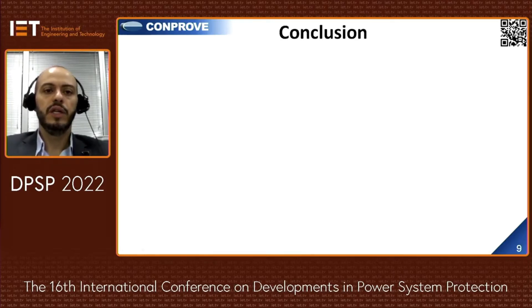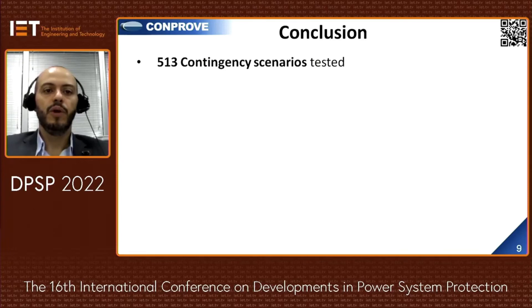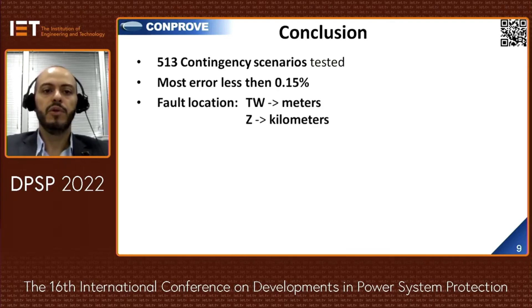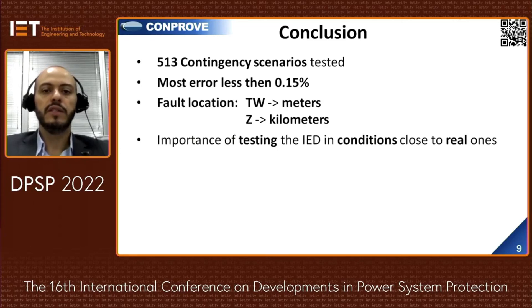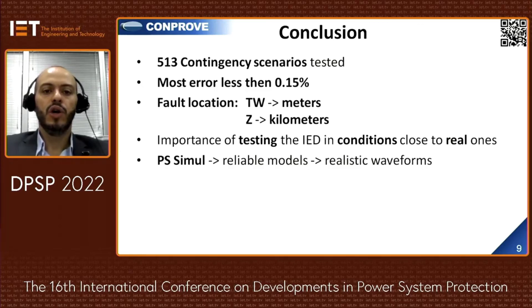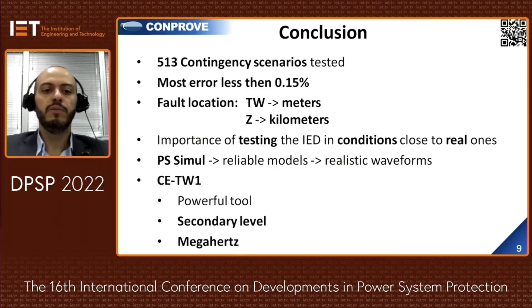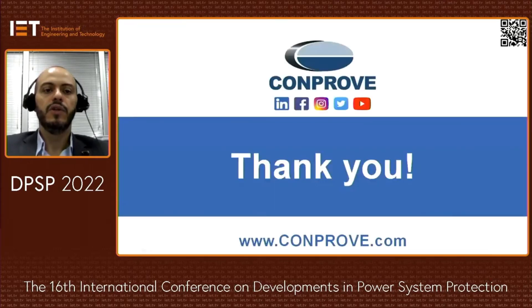Conclusions: 513 test injections were performed. Most location errors in meters were less than 0.15%. TW location errors are on the order of meters, while impedance methods reached the order of kilometers. It is very important to test the IED under real conditions. The power system simulator, with reliable models of electrical system components, results in realistic waveforms. The CETW1 proved to be a very powerful tool due to its ability to generate voltage and current signals at the secondary level in megahertz. Thank you for your attention.